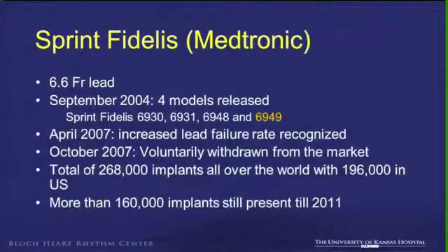I'll start off with the Sprint Fidelis leads, which is a Medtronic lead. It was marketed in September 2004. Very popular lead. At that time the lead size was a pretty good marketing point. It was very attractive. The smaller the lead, the easier it was for the physician to implant.